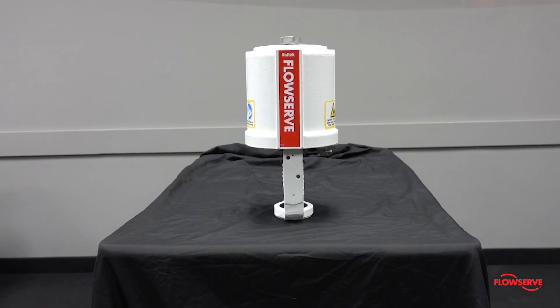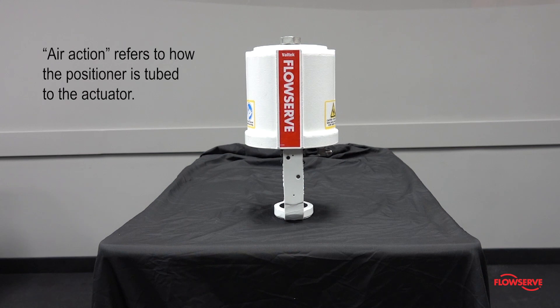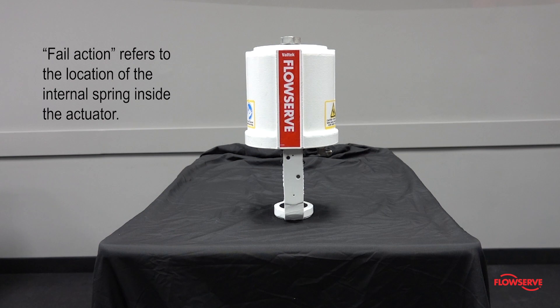The purpose of this video is to demonstrate how to change the fail and air action on a standard spring Valtek VL actuator. Air action refers to how the positioner is tubed to the actuator, and fail action refers to the location of the internal spring inside the actuator.